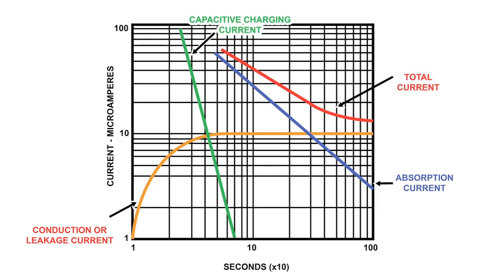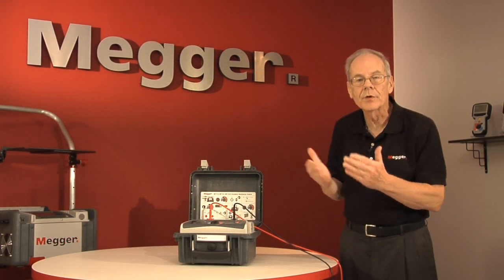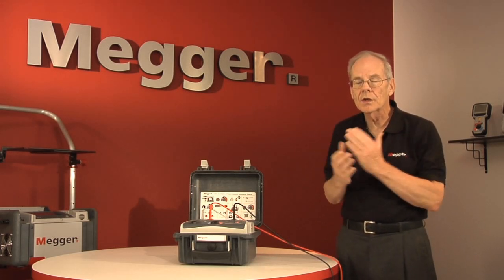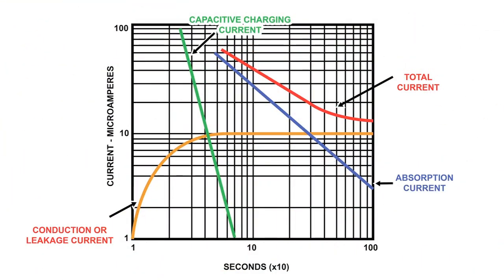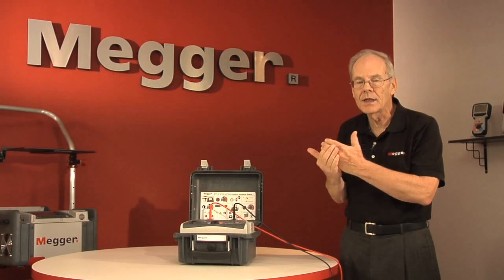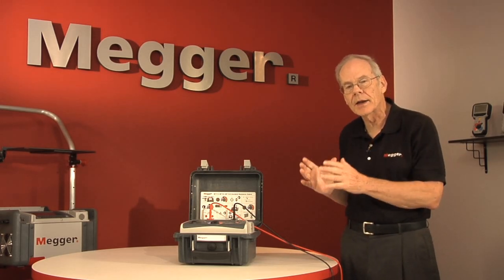Charging diminishes whereas leakage stays relatively constant. So a test item that is pulling primarily charging current will show a much higher number at the end of a time test than at an earlier point. When you create that ratio, you get a number like three, for instance — that gives you confidence the tester was mostly looking at charging current. If you have a lot of leakage, it stays relatively constant, holding the curve down, and you will end up with a ratio somewhere around 1.2 or so, which flags that the test item may not be in great condition.